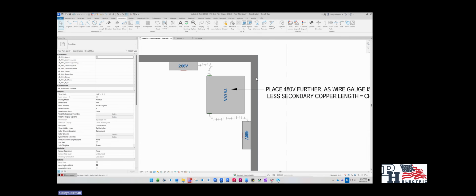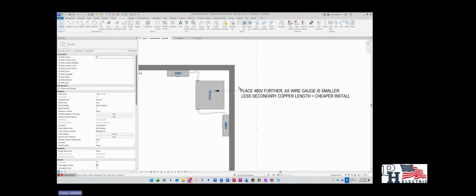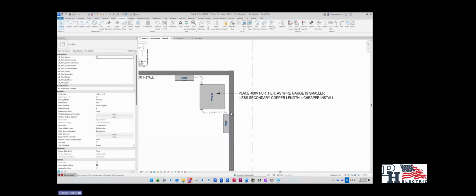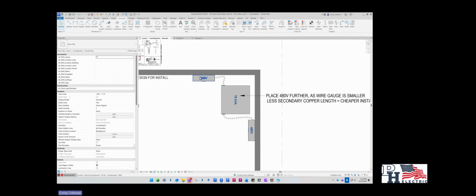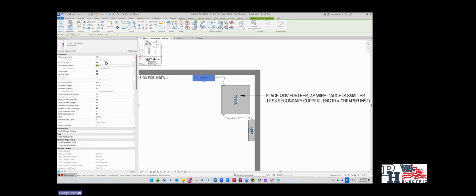Last thing I want to cover is how to place kind of corner transformers. What we want to do is, since the secondary is going to be a larger wire size and gauge, it's going to obviously cost a lot more if we're running it long. So what we want to do is try to keep that distance as short as possible. So we always want to place the 480 volt panel where it has further of a lead, because that is going to be a smaller wire gauge, which would then lead to less copper being purchased and installed. So this would allow you to actually create a cheaper installation versus if you installed it.